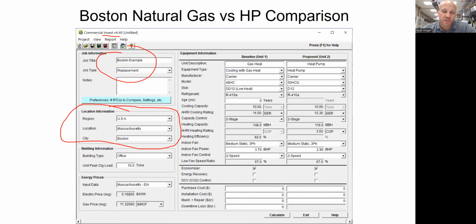Although your state is geographically small, so it may only have a couple. But you put that in so it knows the weather data, and then you put in how much cooling capacity this building needs and what kind of building it is, right? An office versus a school versus a restaurant all have pretty varying needs and varying operating hours. You can't go in here and tell it what the operating hours are. If you want to start getting detailed like that, you need an energy modeling tool. This is just a quickie tool, so it's making giant assumptions for you to make it fast.